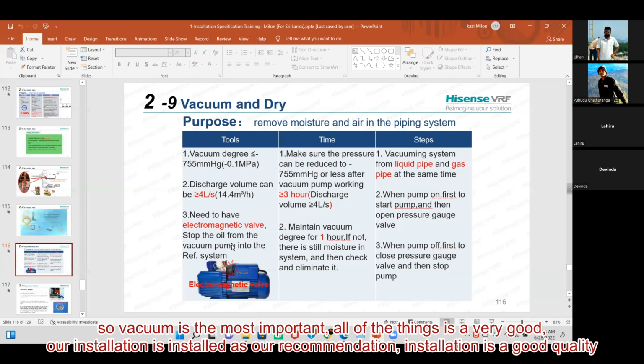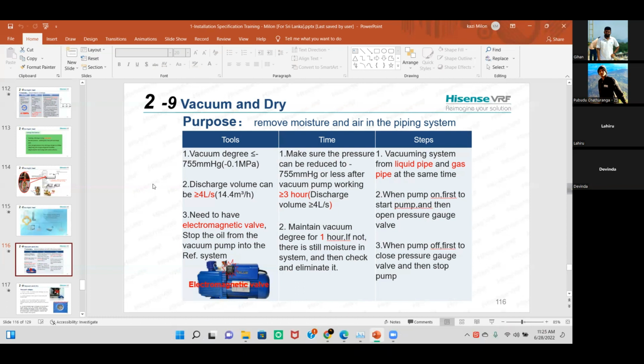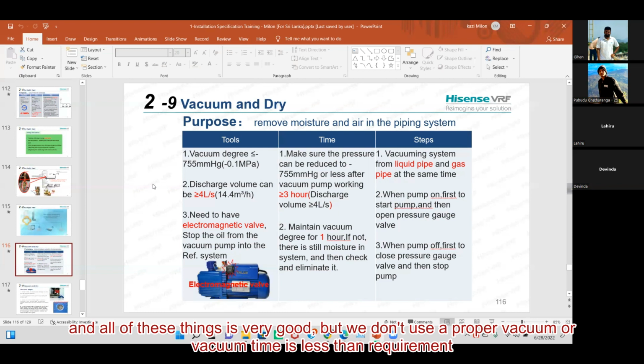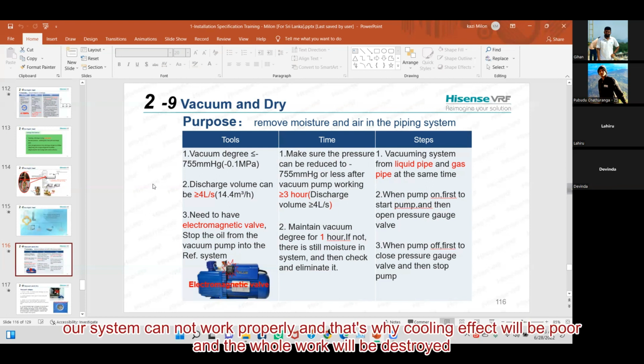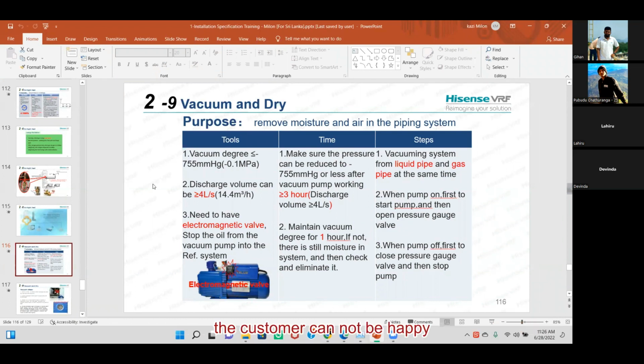So vacuuming is the most important. All of the things are very good, our installation work is as per recommendation, our installation goods are good quality, but if we don't use proper vacuum, or the vacuuming time is less, then our system cannot perform properly. That's why the cooling effect will be poor and the whole work will be destroyed. Then the customer cannot be happy. We cannot get proper cooling effect according to our system. That's why proper time vacuuming is most important.